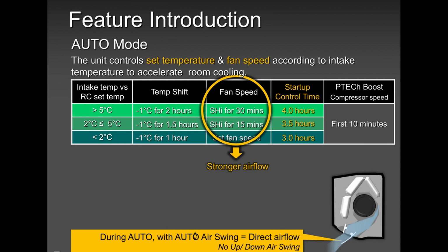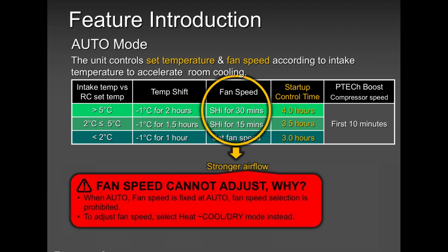So please keep in mind, in auto mode, you don't have many features to play around with because everything is preset. Everything works based on the temperature of the indoor coil. As you can see here, the unit controls set temperature and fan speed according to the intake. The same applies to auto fan, auto fan and auto louver in heat mode, it all works based on the temperature of the coil.